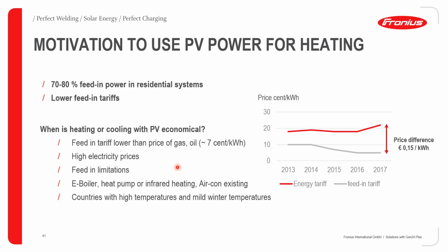So when is heating or cooling with PV economical? It comes in a very economical fashion when the feed-in tariff is lower than the price of gas, in this case approximately 7 cents per kilowatt hour. It's also economical when you have high electricity prices, feed-in limitations, and when you're using heavy loads like boilers, heat pumps, infrared heating, and air conditioners. And of course, it's a very economical option for countries with high temperatures and mild winter temperatures.